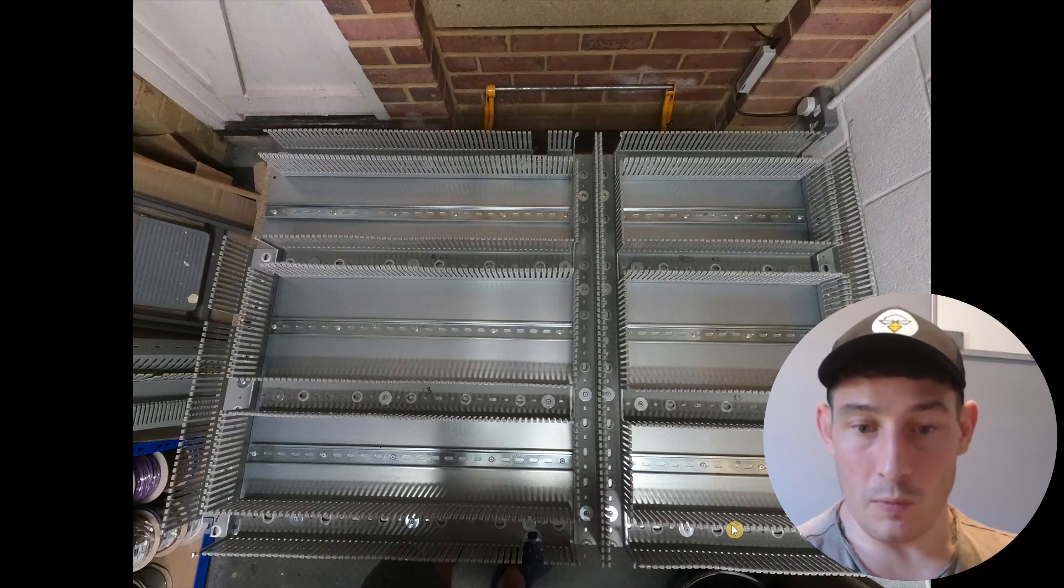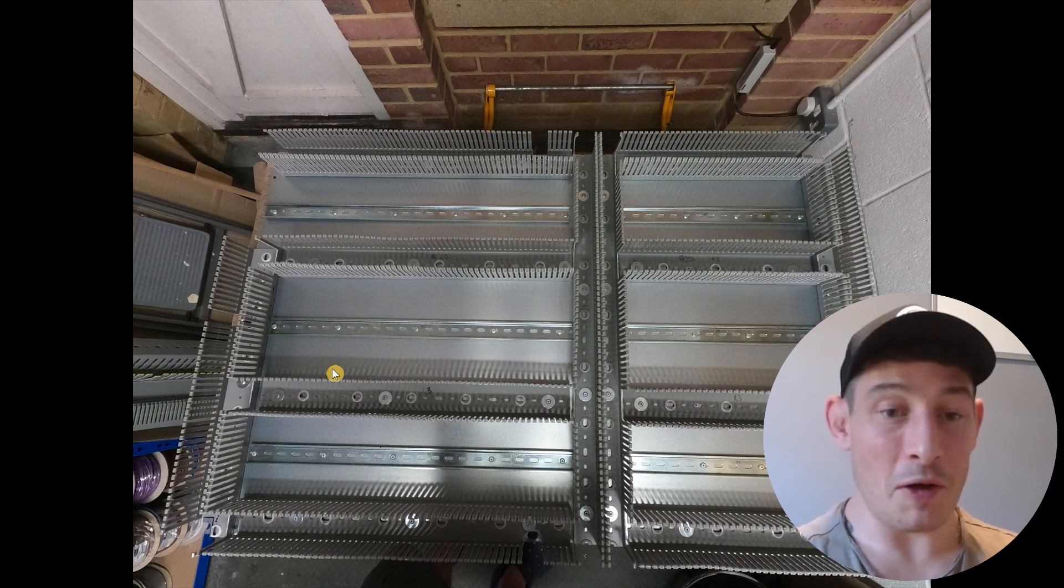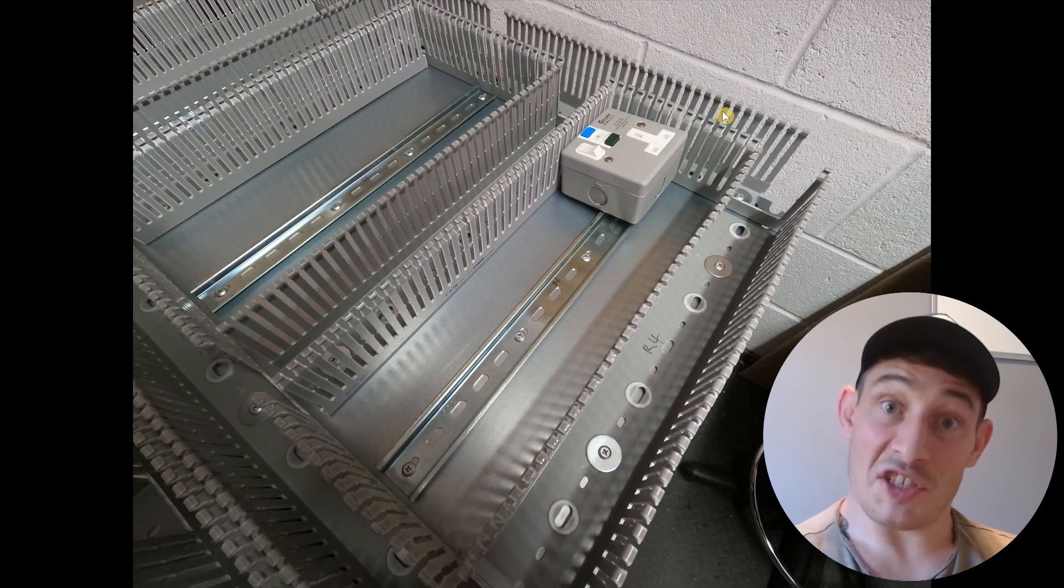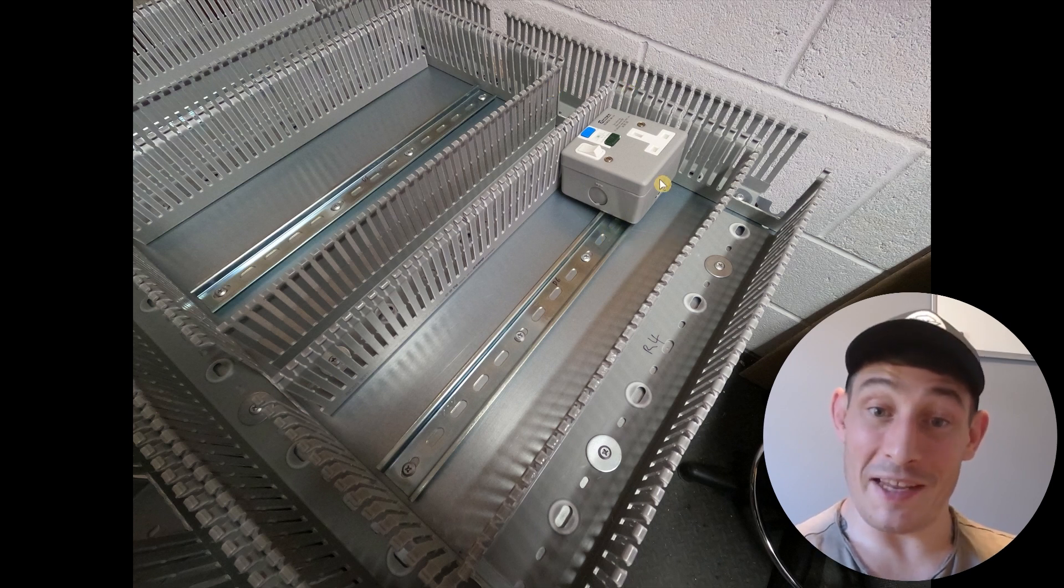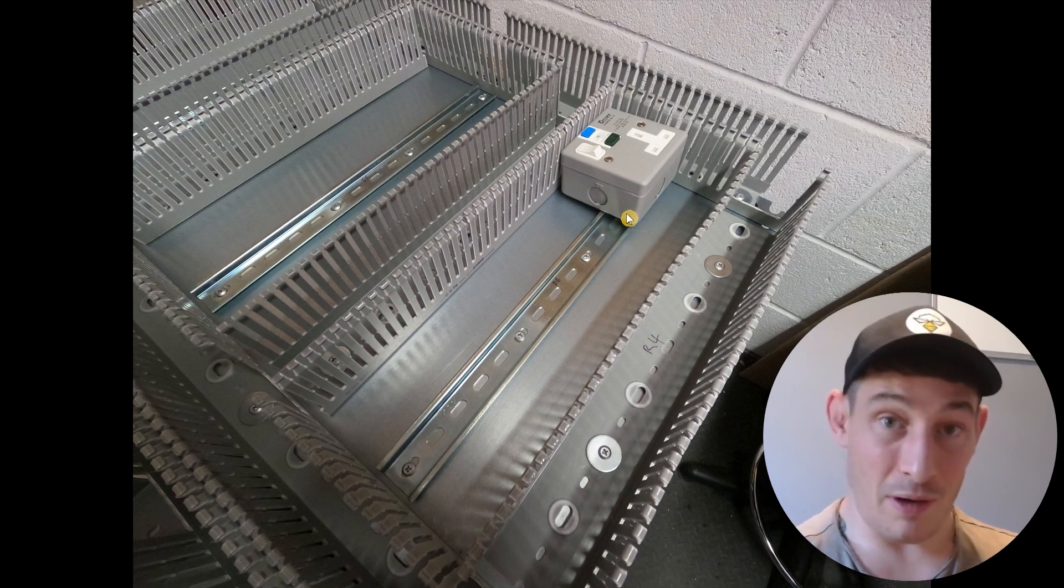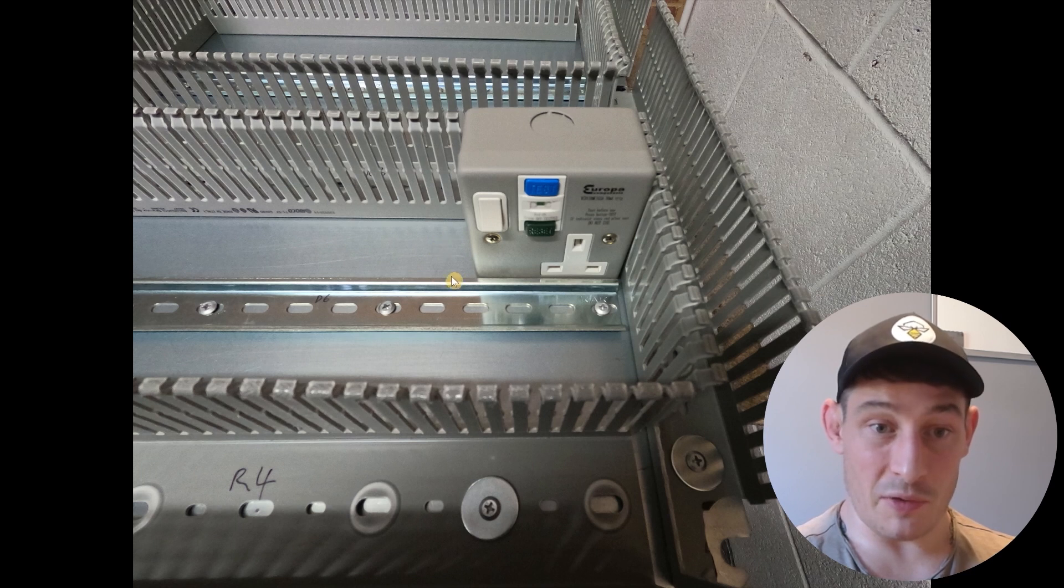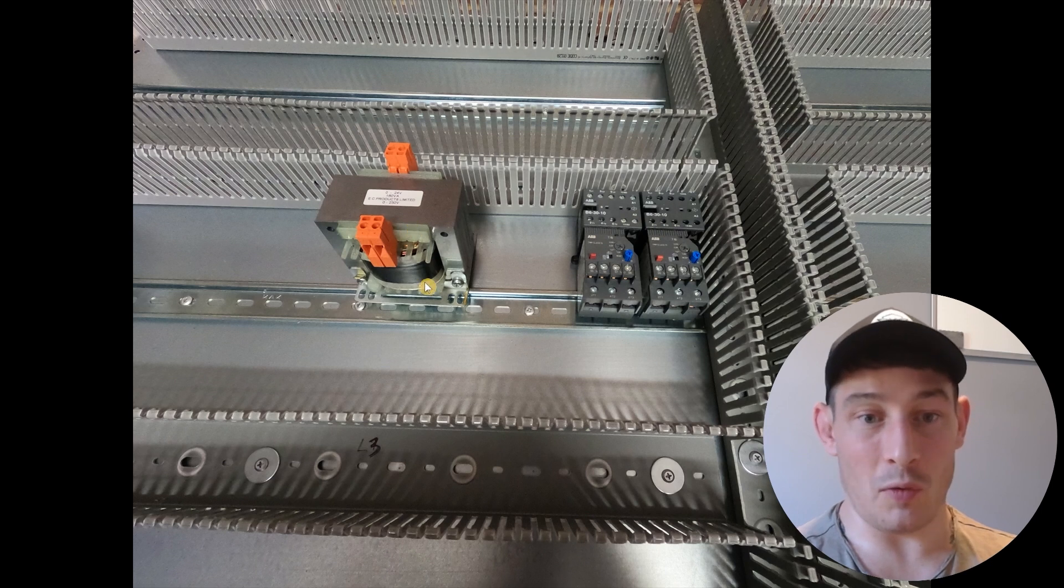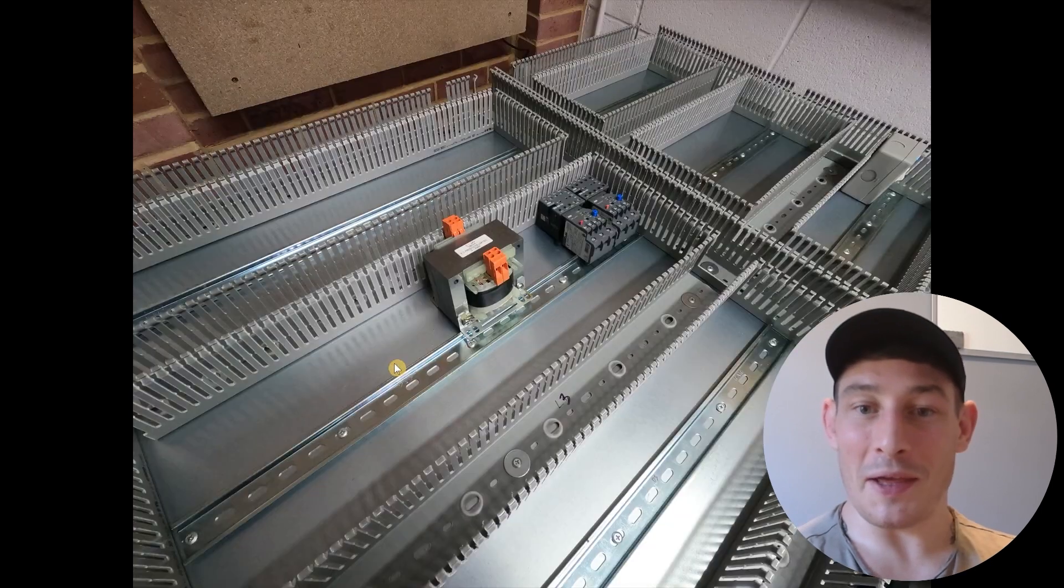Little mistake that I've made and typical I do this kind of thing most of the time. So if you look at the drawing we're actually meant to have a laptop socket or just a socket in general here, but I've made the DIN rail go across that whole section when it should have been cut off here. So that's something that I need to rework. So DIN rail should have ended here and it's exactly the same thing with the contactors and overloads and the transformer. As you can see I've run the DIN rail all the way along, so a couple of things that needed correcting there.